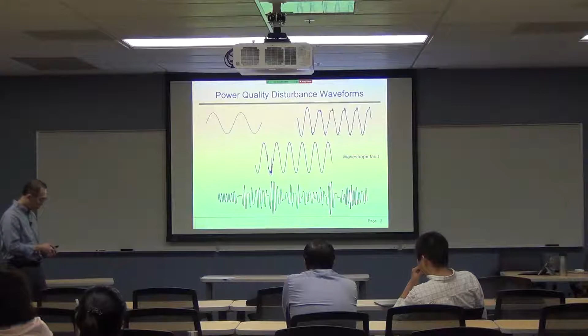Now, where are these disturbance waveforms captured? First, they are captured using power quality monitors, which I will show you a little bit later. This is essentially a distribution feeder. What you're looking at is one of 4 feeders, with a normally open switch breaker, supplied by a distribution transformer, which is fed by 138 kV transmission lines. Power quality monitors can be located practically anywhere you like, but typically they are located right at the feeder head.